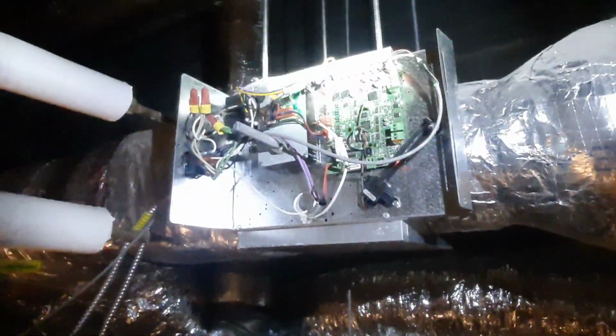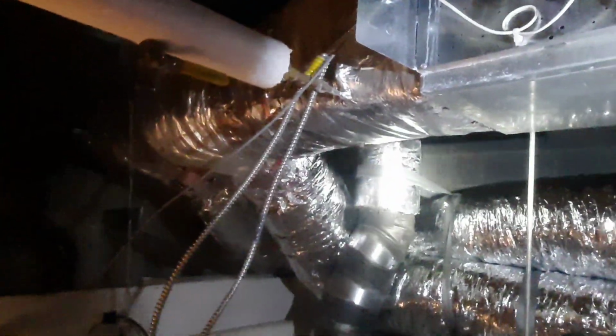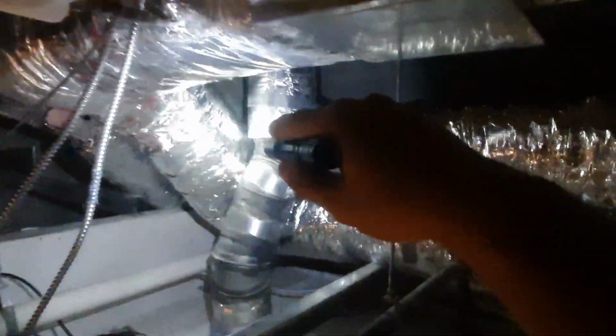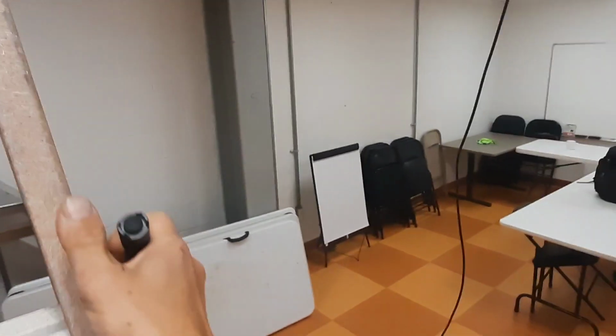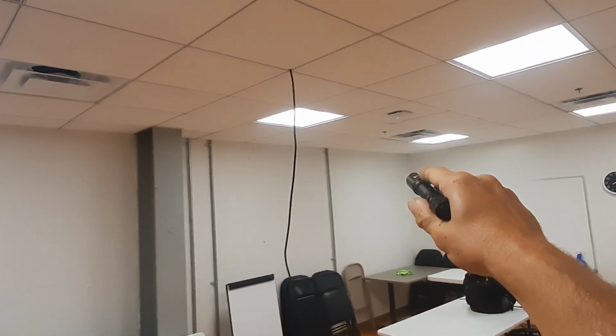It's been abandoned. Years ago, they actually had, so there's my duct there that I cut off. The registers out there were condensating because it's unconditioned and we were blowing 55-degree air through it. So I just closed the VAV damper at that point because it wasn't being used. Anyways, they made this conference room. They needed a solution for air. So I came yesterday. We added 2 flex runs and 10 inch. So I just split them up evenly, put them in the same spot on the other side of the room.